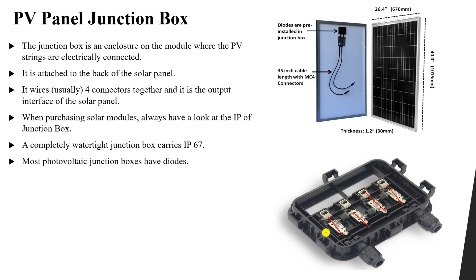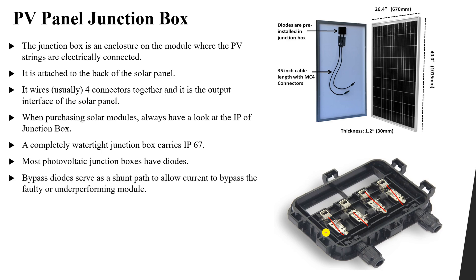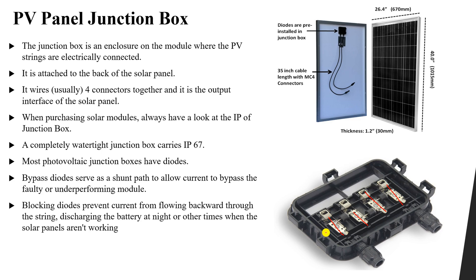Most photovoltaic junction boxes have bypass diodes, which form a shunt path to allow current to bypass a faulty or underperforming module. If there is a fault or shading effect in part of the panel, the bypass diode will bypass that section. The blocking diode, found inside the charge controller, prevents current from flowing back through the string — stopping the battery from discharging back through the solar panels when they are not producing power.